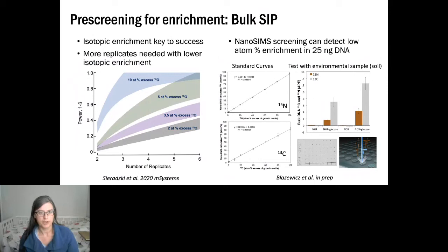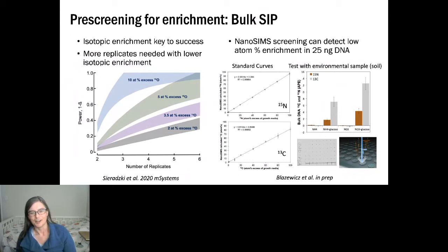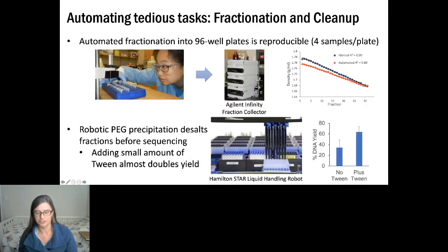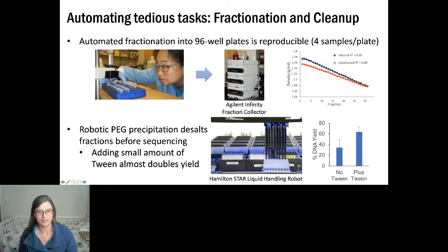The second part of this process is automating the actual fractionation. Originally you take the tube and drip fractions manually into collection tubes — super tedious. We used an Agilent Infinity fraction collector to automatically drop fractions into a 96-well plate. Typically four samples go into a plate, putting us in a high-throughput format where we can process multiple samples simultaneously. This automated process is very comparable to manual fractionation.